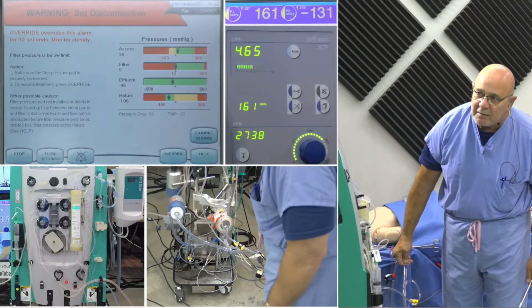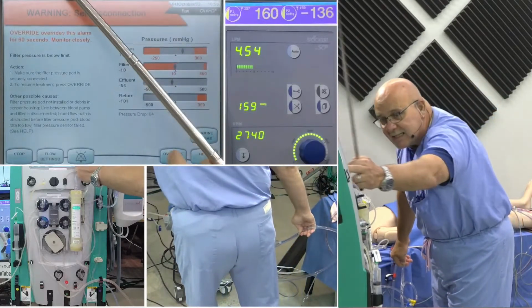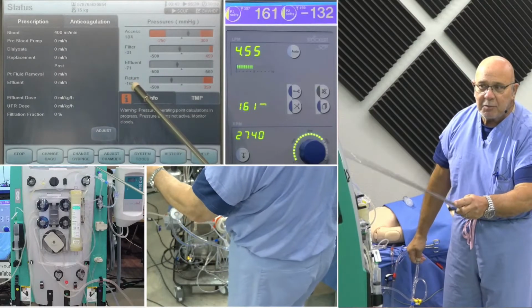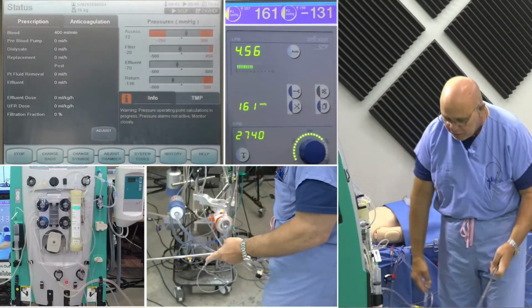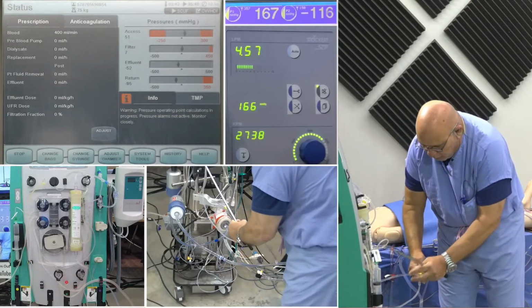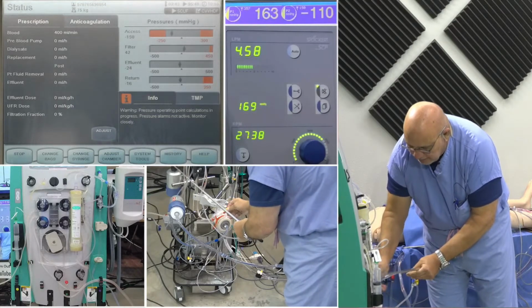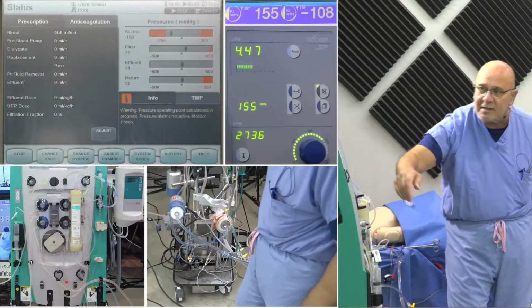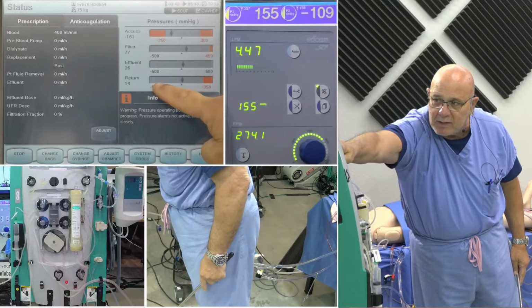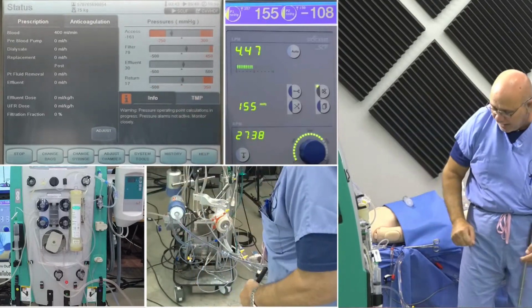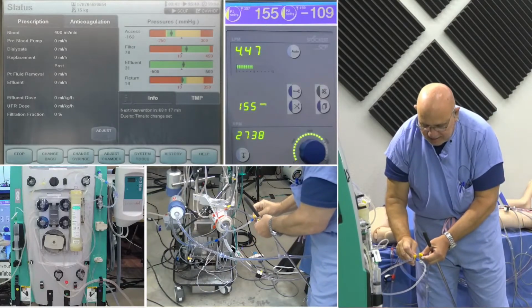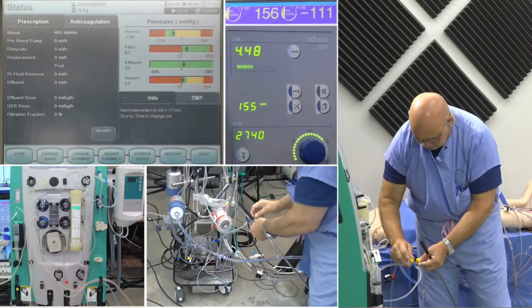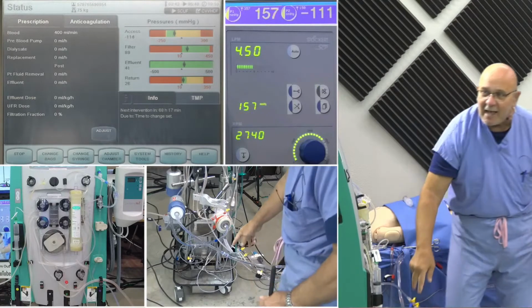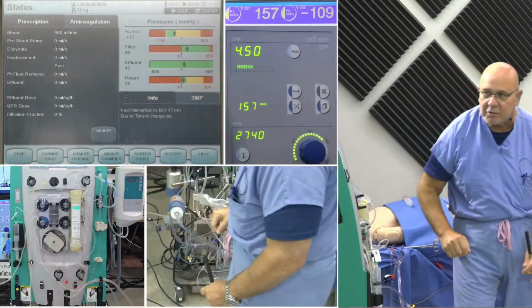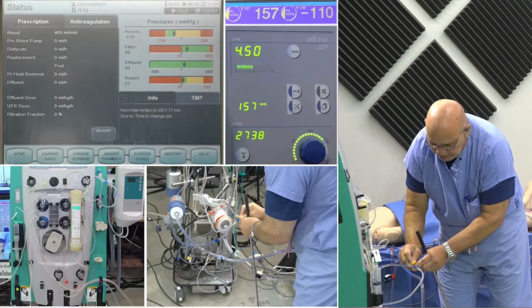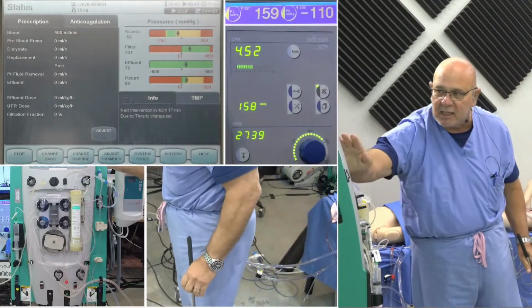You see everything becoming more negative, and eventually it believes the set has disconnected. And the reason it believes that is your return pressure should be a positive number. So what I do is I have it going through the circuit completely with everything, as I said, wide open. I want that effluent pressure to be positive, and I want that return pressure to be a little more positive. So this is what I do. I put just a slight turn on this stopcock, which is my return line. And that is going to increase my return pressure, which will increase my effluent pressure. And so it's a very slight turn, not very much, but just a little bit of resistance.